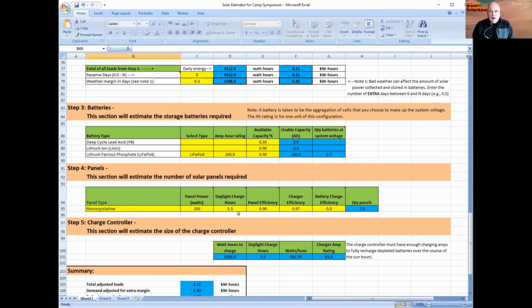And most people use 5.5 to 6 sun hours out on the playa. You can kind of ignore these efficiencies for right now, but all the efficiencies and inefficiencies are built in. And it tells me I need 7 of those panels to run this system. Obviously, I could use a bigger power panel and use fewer of them, or I could use 100-watt panels and I need 14 of them.